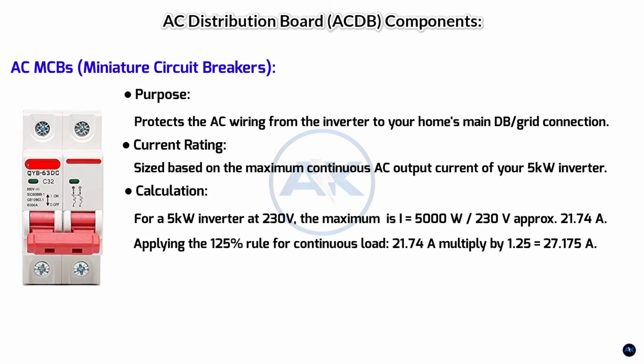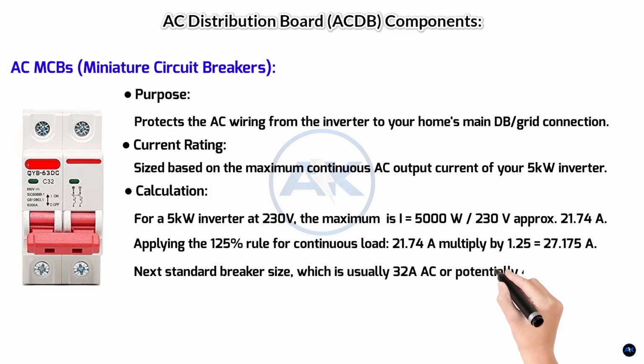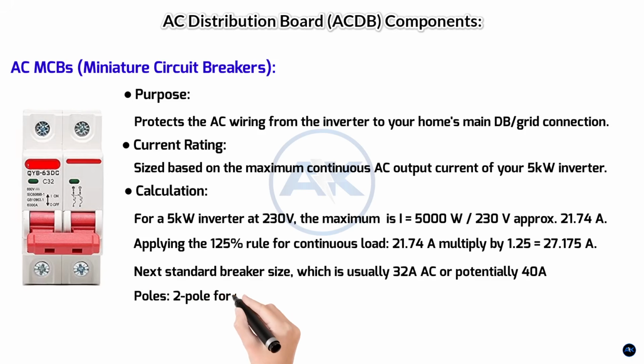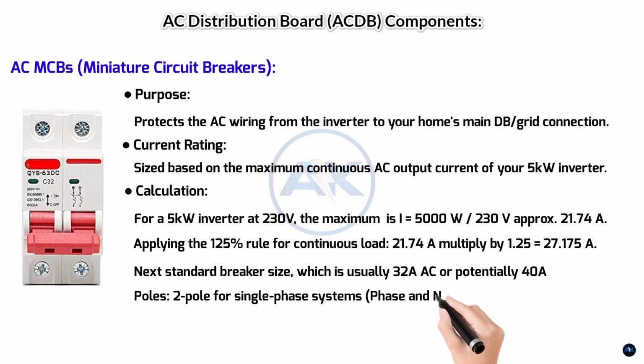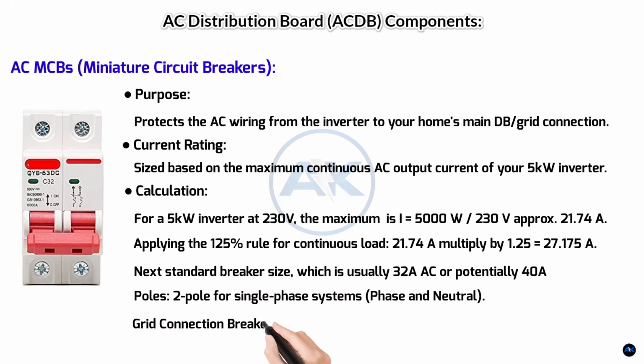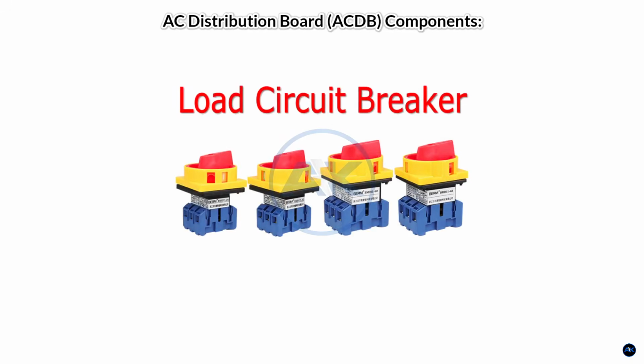You would typically select the next standard breaker size, which is usually 32 amps AC or potentially 40 amps AC, to provide more headroom depending on inverter surge capabilities and local code. Poles: 2-pole for single phase systems, phase and neutral. Grid connection breaker: optional but recommended. If you have a separate breaker for the grid connection for export-import, it would also be sized similarly to the main AC output breaker. Load circuit breakers. These are for individual circuits within your home, protecting specific loads: lighting, power outlets, and heavy appliances.